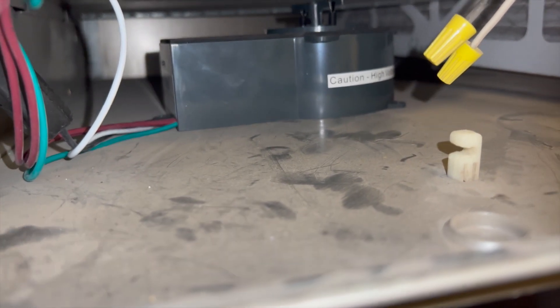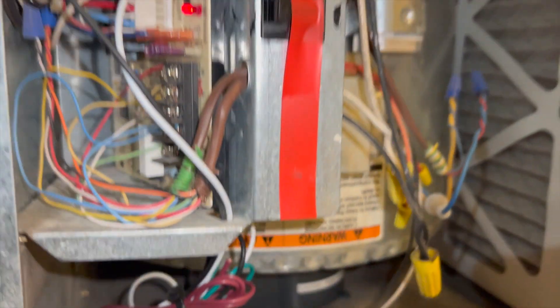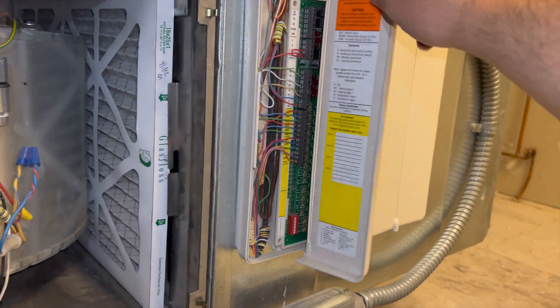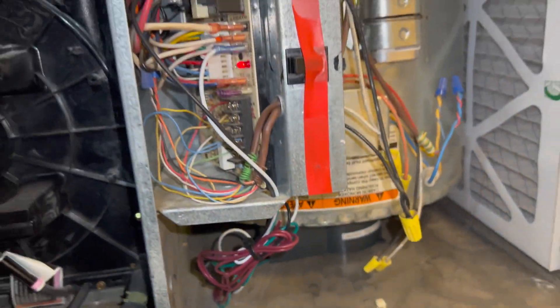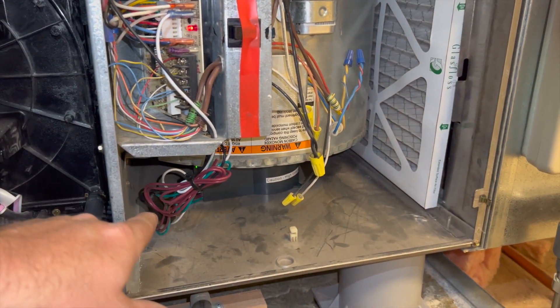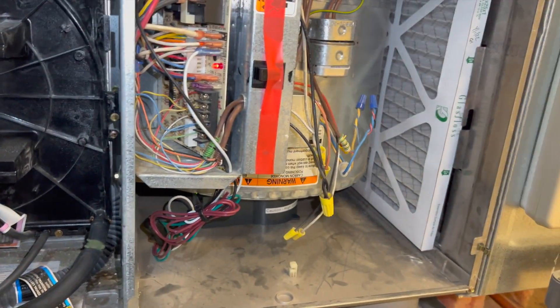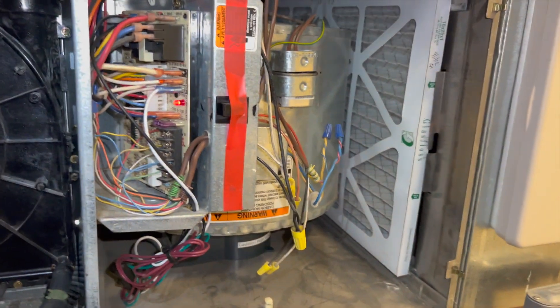There's a little light on the end of the unit. We're going to power this up — the light won't come on unless the fan is running. As you can see there's no green light yet because the fan's not running. This has one of those Carrier communication zone things, so it takes a minute before it calls for fan. Now it's calling for fan — and there's our green light. When it's not calling for fan it kills the power, nice and clean.